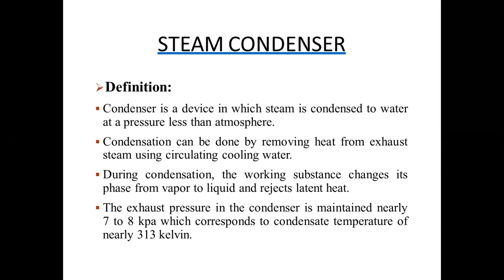A condenser is a device in which steam is condensed to water at a pressure less than atmosphere. Friends, atmospheric pressure is 1.01325 bar. So the pressure inside the condenser must be less than this pressure. Condensation can be done by removing heat from exhaust steam using circulating cooling water. During condensation, the working substance changes its phase from vapor to liquid and rejects its latent heat. The exhaust pressure in the condenser is maintained at nearly 7 to 8 kilopascal, which corresponds to a condensate temperature of nearly 313 Kelvin.